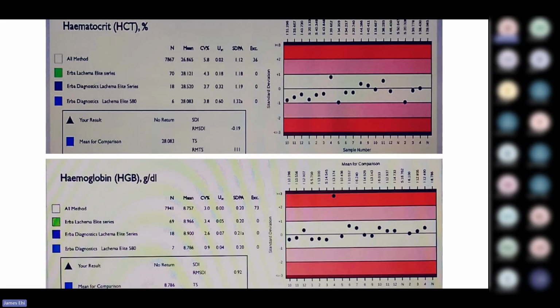And if it gives me the correct result, that means this current batch of EQA material is faulty. Then I will still accept my patient sample based on acceptability of the previous runs, that is the previous EQA. So if the EQA material is faulty, you will also detect it just as if your internal control material were faulty. Do a recheck or ask a neighboring lab, a lab that you are associated with. You can ask, can you please help me with an aliquot? Then you know whether the sample in your custody is compromised.